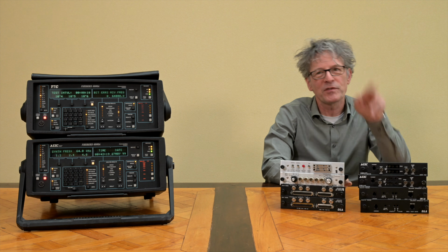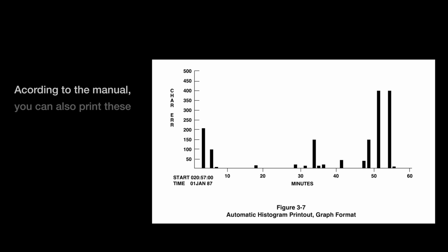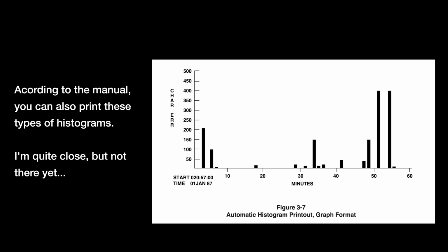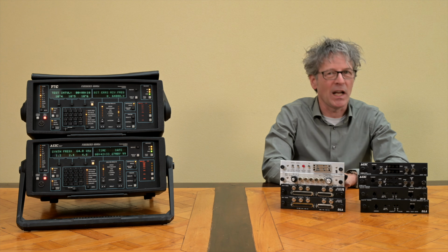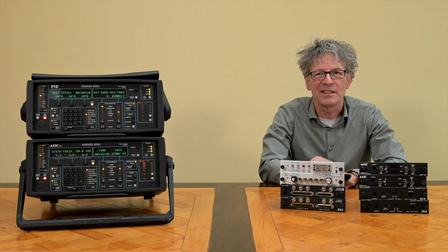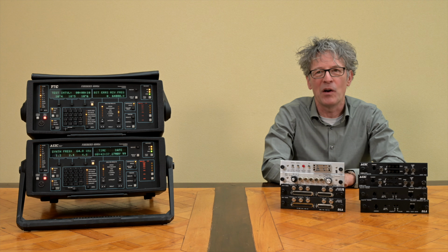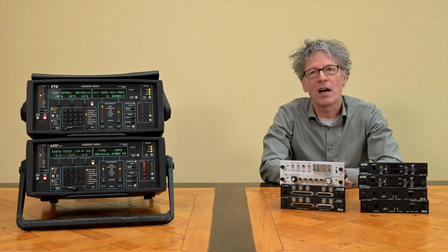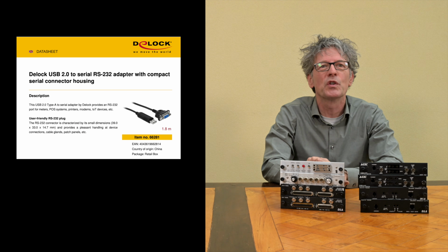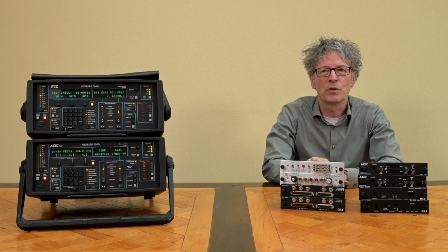It can create tables where you see, like, every hour or so the average of certain measurement parameters. But it can also output all the measurement parameters at once or a selection of them. I don't have any serial printers lying around in the house, but I hooked it up to a computer with an RS-232 to USB converter and used a computer terminal program.